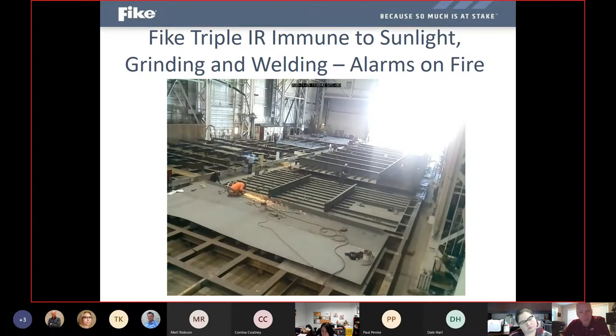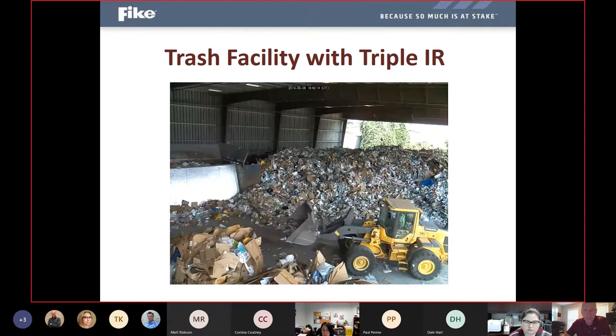So here he's still working on lighting up his little piece of product there. And as soon as there was enough flame present and that energy reached the IR detector, you can see the screen starts to blink. That would be the flame detector now going into alarm because of that fire that was present. So its ability to rule out and ignore false sources of radiation, but to really trigger or focus on an actual fire event, is very impressive with these detectors.